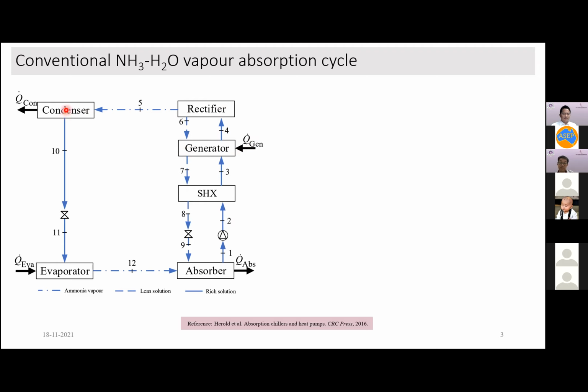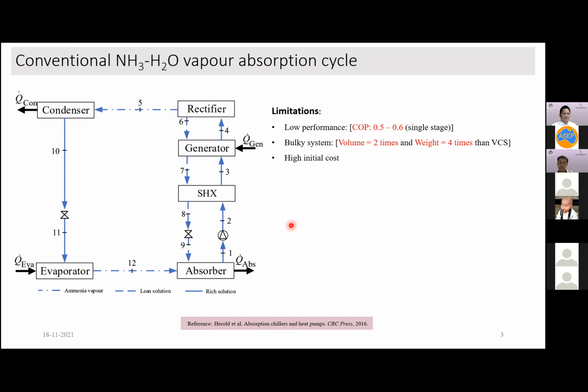In the condenser, the ammonia vapor rejects the condensation heat to the heat sink, and the saturated liquid passes through a throttle valve and enters the evaporator. In the evaporator, it receives heat from the cooling load, and the vapor is absorbed in the absorber. This configuration has limitations. The first is low performance, in the range of 0.5 to 0.6. The system is bulky: approximately two times the volume and four times the weight of the conventional vapor compression system. It also has a high initial cost.